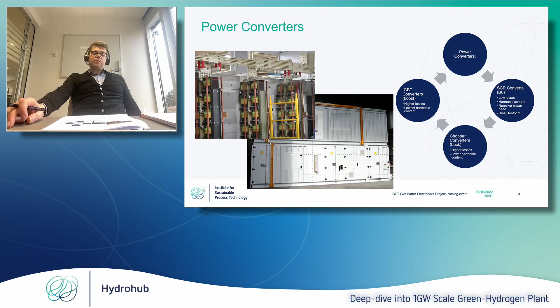It's cheap and efficient and very reliable, but could give you some challenge if you have a requirement for flexible hydrogen demand, or flexible fluctuating power from a wind turbine or PV power plant. You can add an IGBT chopper to get a more flexible converter, or go all the way with an IGBT converter type, which gives you a more flexible solution when you look into harmonics and reactive power requirements.